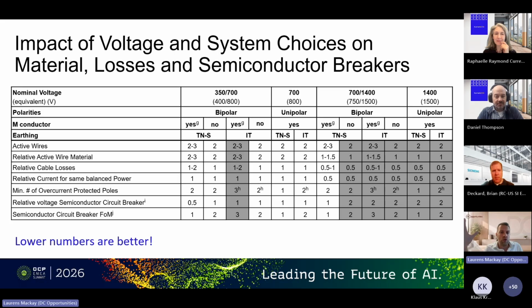And then semiconductor breakers are in principle a bit pricey, and they also have impact on losses of the system. And there's a multiplicator there that's basically the current that you have to protect, the voltage that you have to protect, and how many of those breakers or switches you need. And the multiplication of those is this figure of merit that we have on the bottom, and basically what you can see is as you go up in the voltage, yes, you need more voltage in your thing, but then also the current goes down. So there's different systems, but then the different earthing systems, they result in different voltage semiconductor area that you need in your breakers. In general, for all these tables, you can find them in the white paper. Lower numbers here are better.